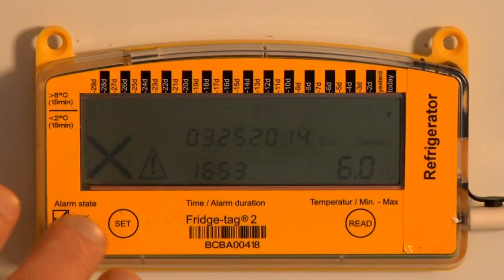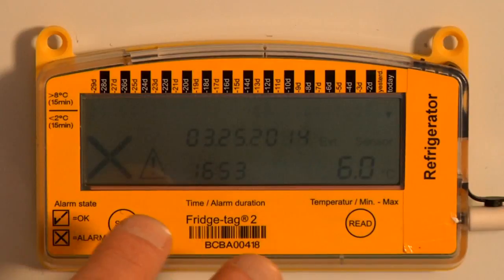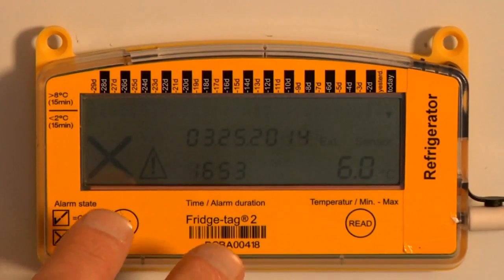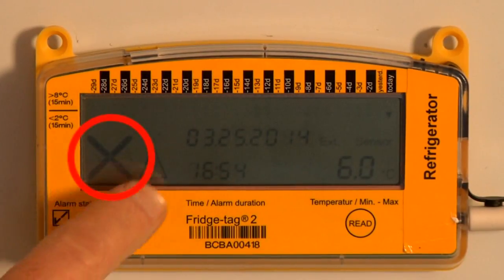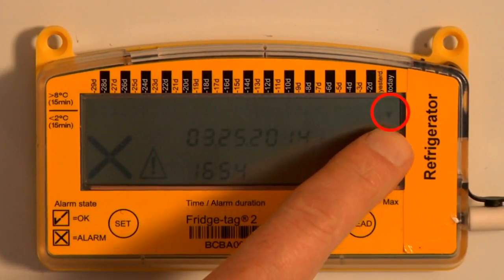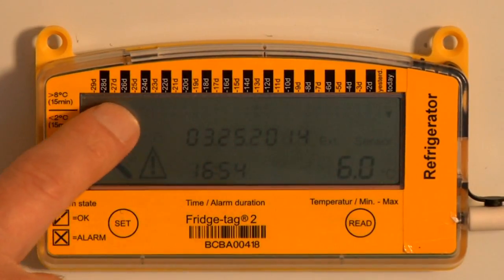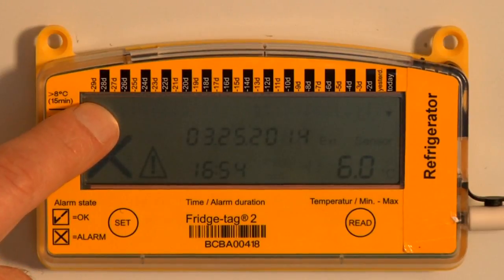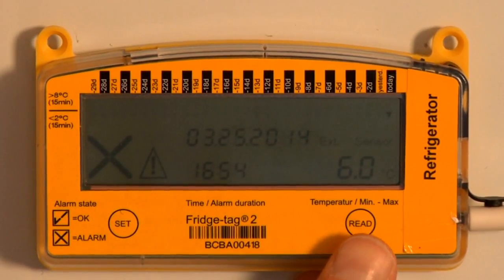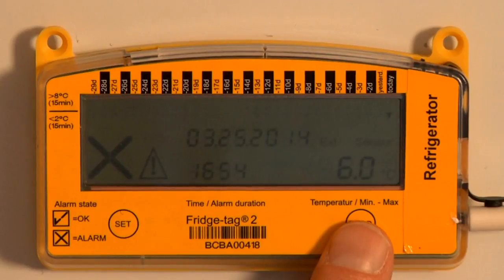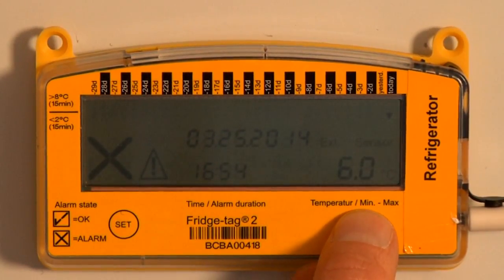A quick snapshot of this storage unit tells us that we've had an alarm in the last 30 days, it hasn't been checked, and it happened today because the down arrow is on today. But the previous 29 days were okay. In order to see what the temperature readings were today, we would press the read button.